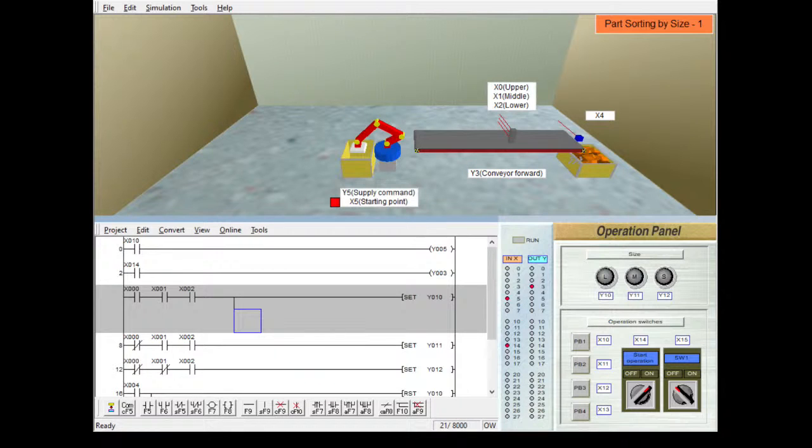For counter you also have up to 256 counters in your PLC, from 0 to 255, and of course these counters can be addressed from C0 to C255. Then you can set the count duration you want them to count. So if you say C0 K, for instance, 100. That's what you want.